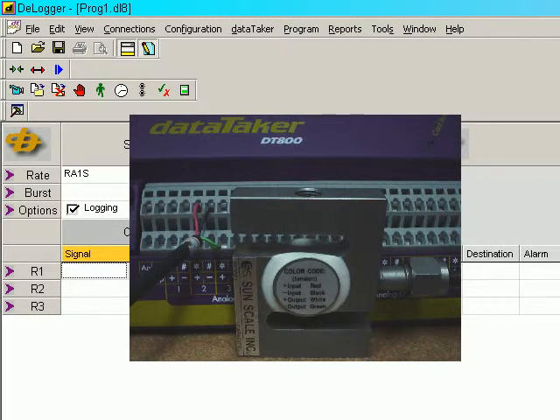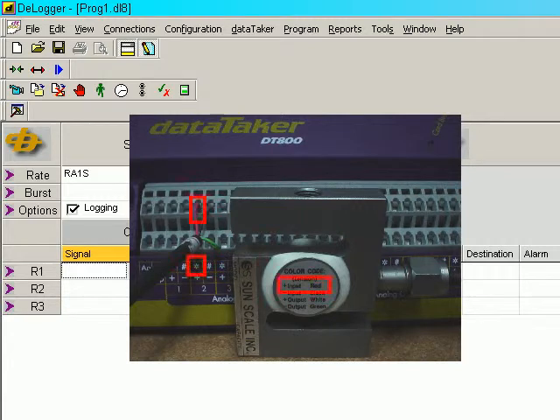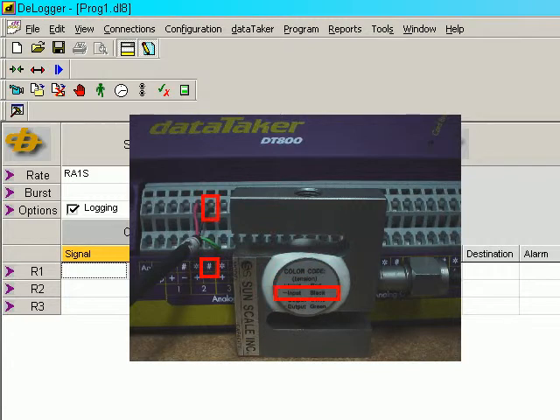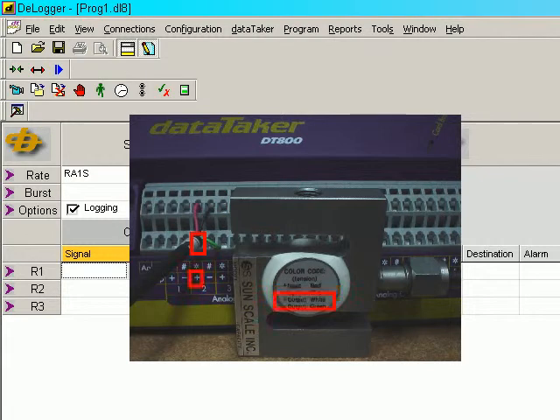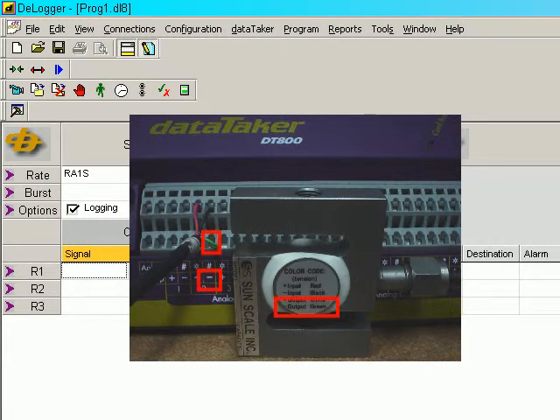When we inspect the outside of the load cell, we see that the plus terminal, the red wire, is connected to the star input on channel 2, whilst the minus input terminal, which is the black wire, is connected to the hash terminal. The plus output terminal is connected to the plus terminal on channel 2, whilst the minus output is connected to the minus output on channel 2.